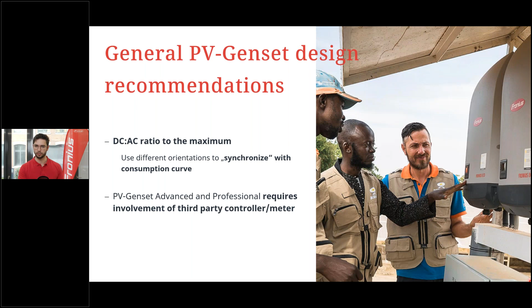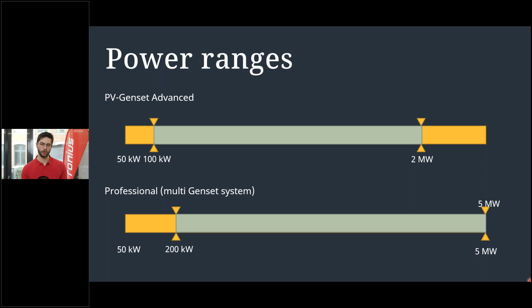And we have heard about PV-Genset Advanced and Professional, which require involvement of third-party controllers and meters. Like I mentioned, Comap, Dive, and Elam would be partners for that. Power ranges would be for the advanced solution up to 2 megawatt. Like I mentioned, then we have just a simple controller which gives the demands to the inverters. And if we want really multi-megawatt systems up to 5 megawatt, for example, then we typically go for a professional solution, because then it does make sense to have also a controller unit on the generator itself, on the diesel generator. All right, so you can see the limit is quite high up, so you can do quite big systems with PV-Genset solutions there.